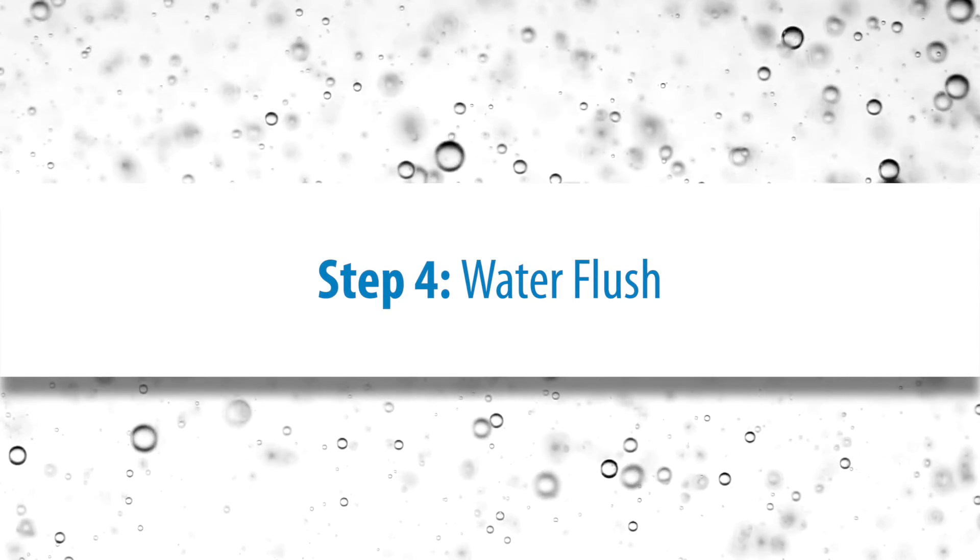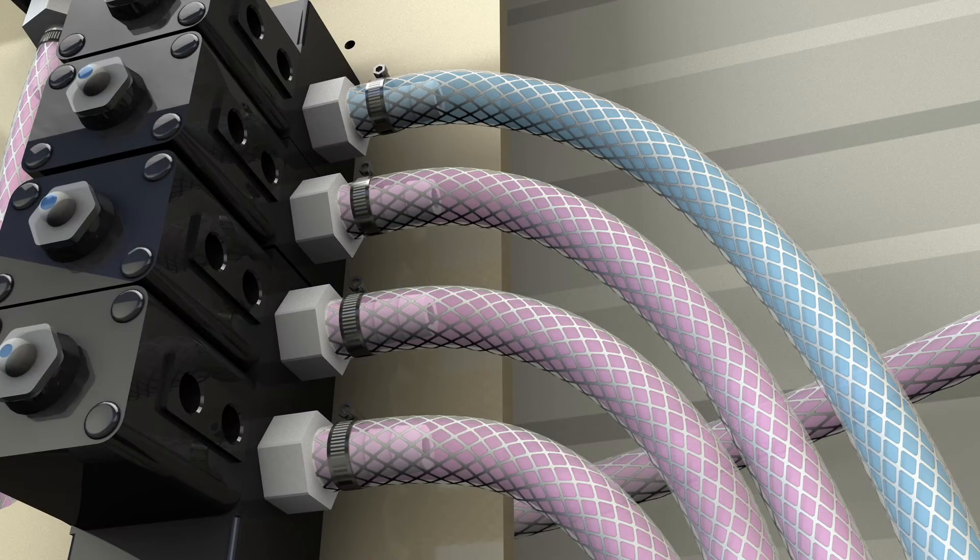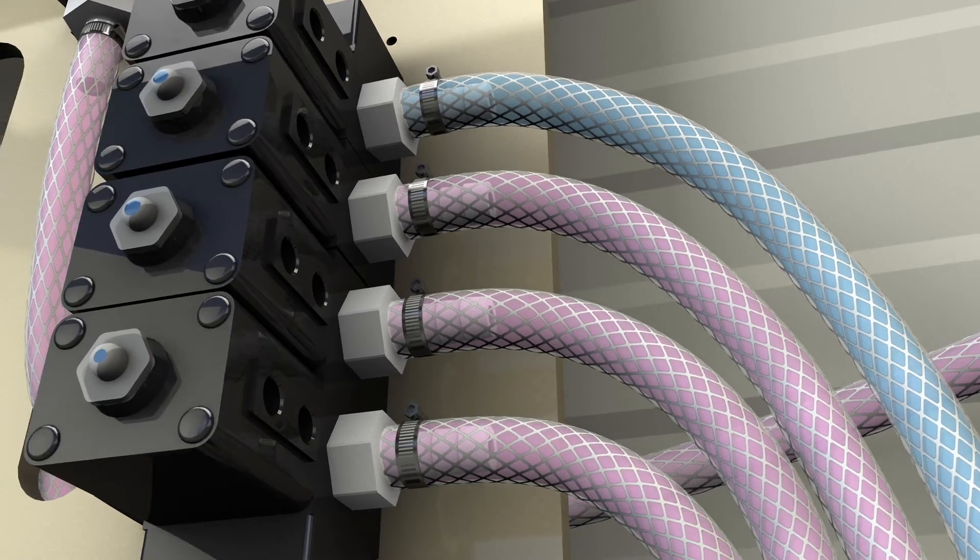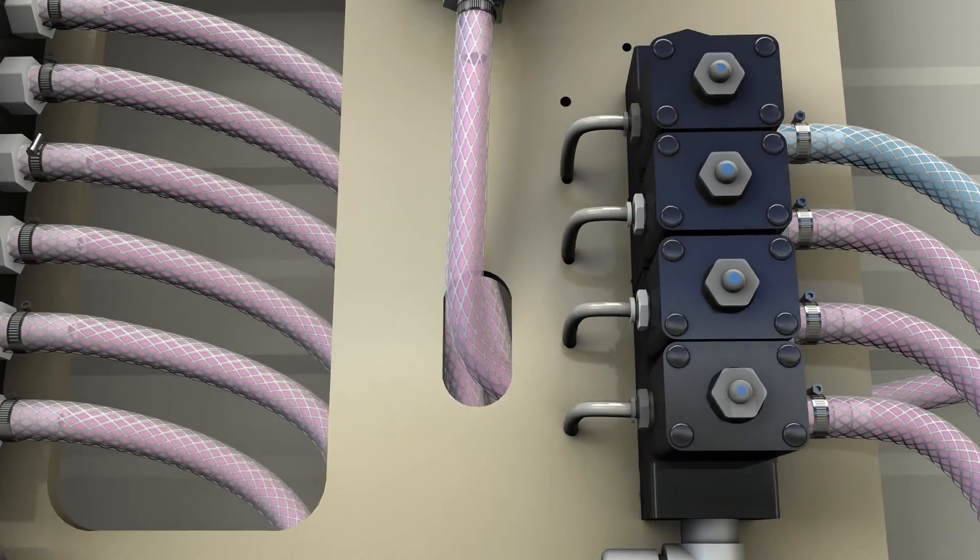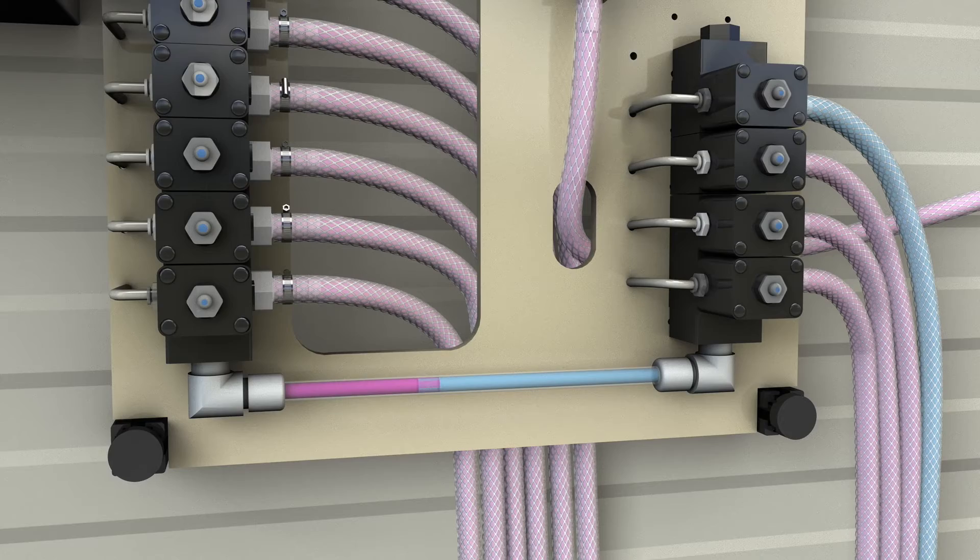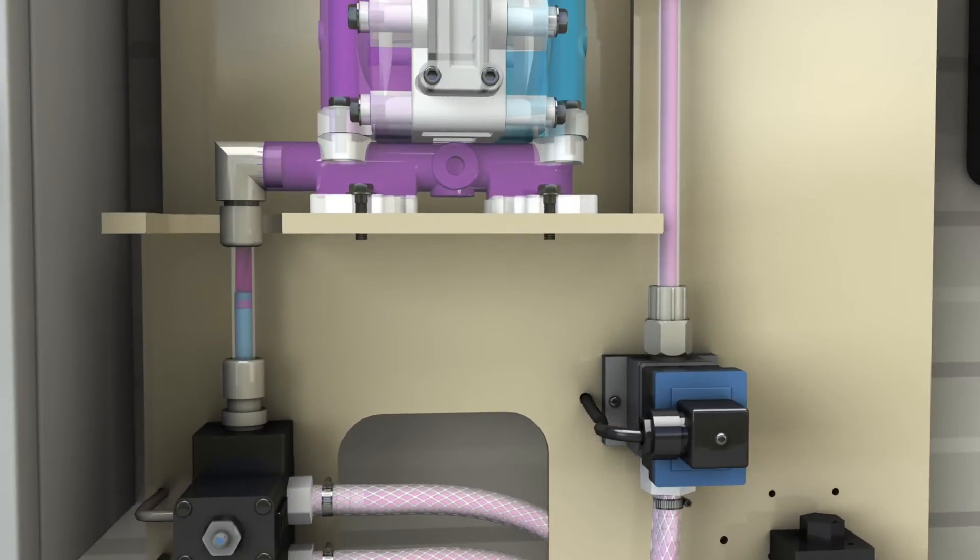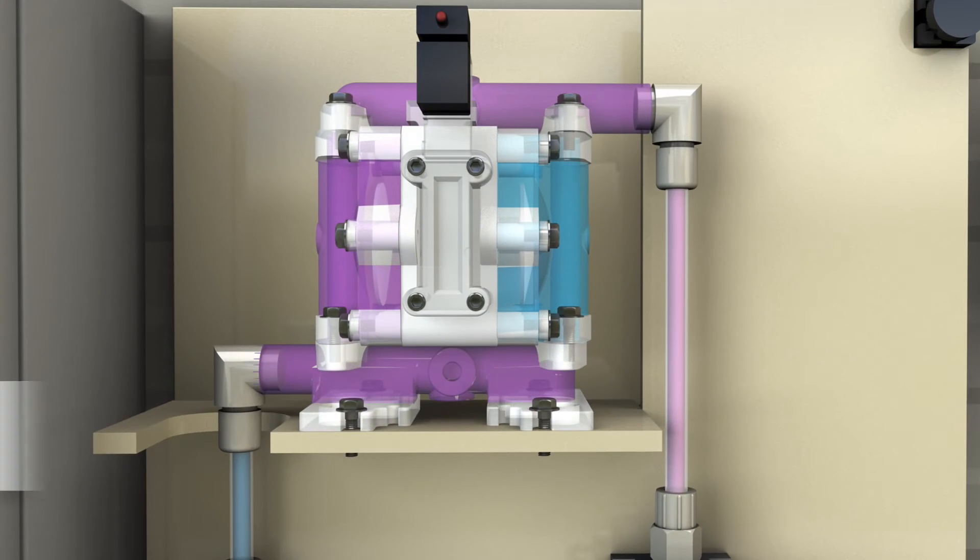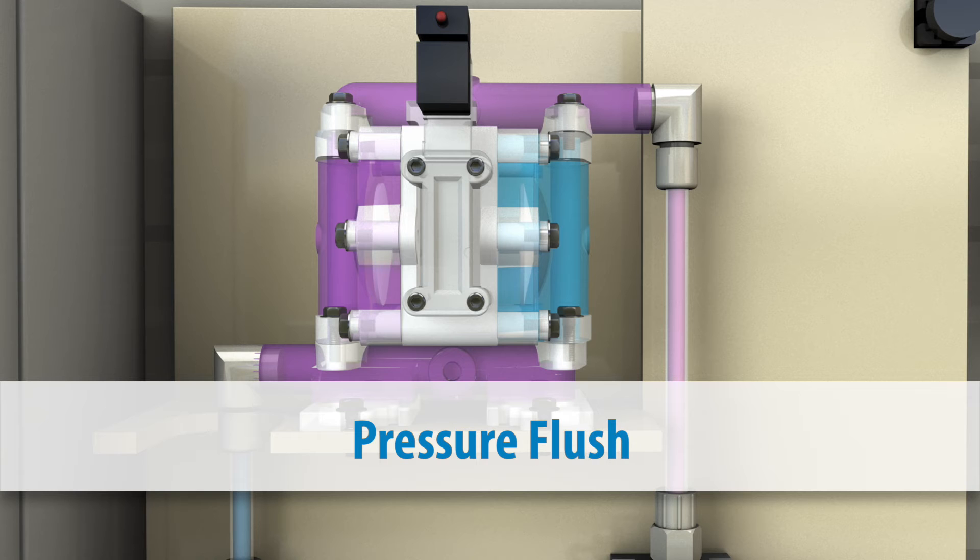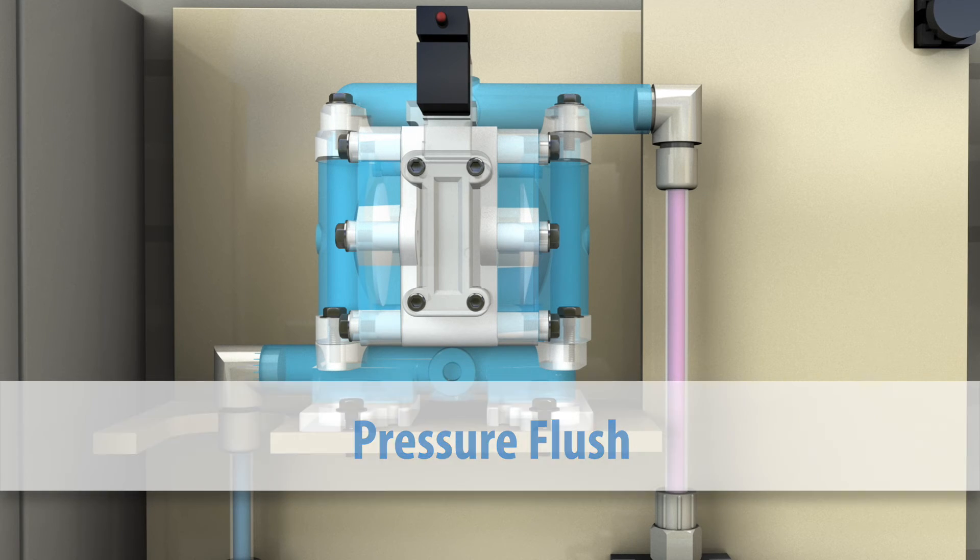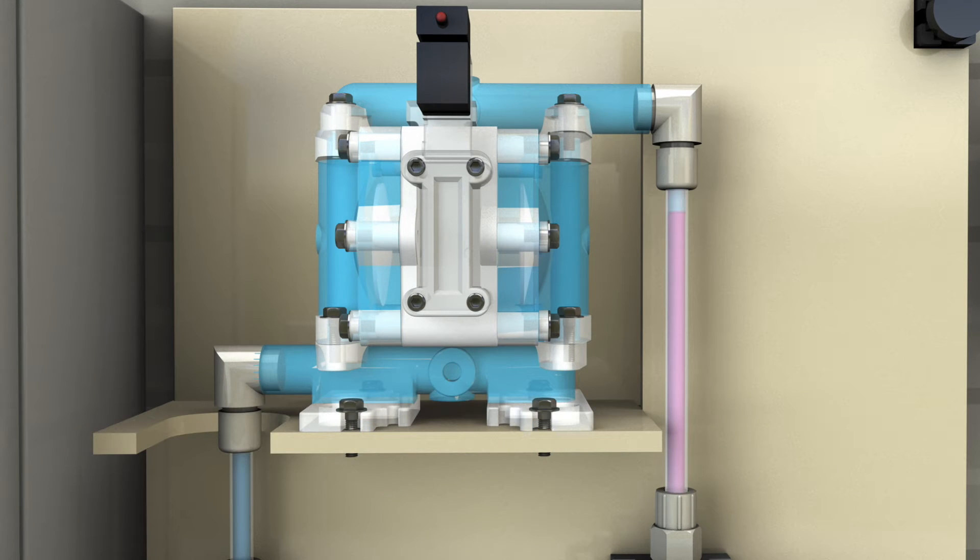Step 4: water flush. The chemical valve is closed at the collector and the water valve is opened. The water flush can be completed in two different ways configurable via the system's setup menu. In a pressure flush, the pressurized water supply flows through one cavity of the pump, flushing the chemical to the washer. Halfway through the flush time, the pump cycles to allow the remaining cavity of the pump to be flushed.